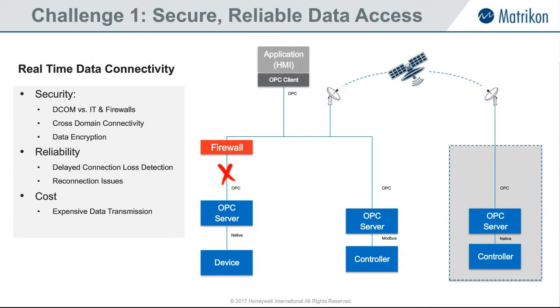The problem there is that, if the firewalls are being put in to limit access to ports which people could potentially hack, or systems can get through which shouldn't, then of course you also start shutting down the DCOM ports, because the underlying DCOM communications are what gets attacked. And yet, if you need communications with the OPC server, well then of course there's now a struggle between operations and IT, because one needs the data, the other needs to keep the system secure. So that generally causes issues.